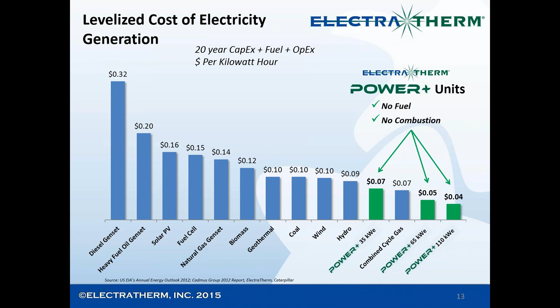Here you can see the three product lines. Starting at the bottom, we have a 35 kilowatt system, a middle 65 kilowatt system, and the 110 kilowatt system. These three output levels can be packaged with a cooling circuit or standalone, since an organic Rankine cycle needs cooling. That's the radiators shown in the top and bottom pictures, and we can fully integrate that for you at ElectraTherm - everything plumbed, with a pump, expansion tank, and all the controls talking to the radiator.